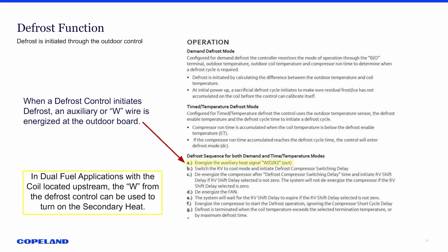Defrost function: when the defrost initiates, and we've already discussed this, I'm preaching to the choir here, I think. It's the energizing of the auxiliary signal going out from the defrost control that allows that dual fuel, or that second stage, to kick in.